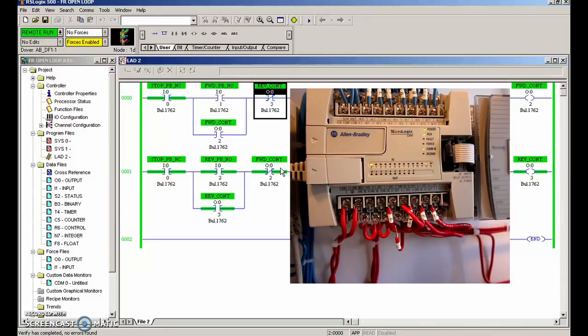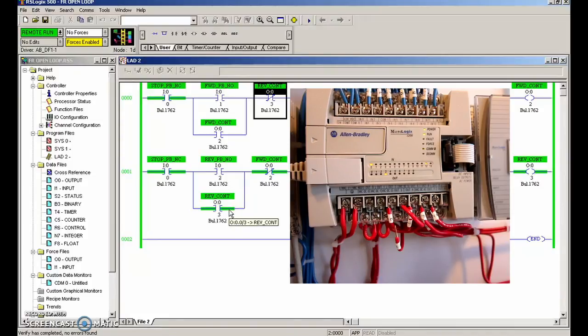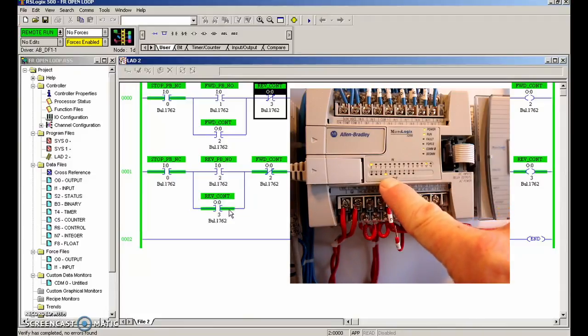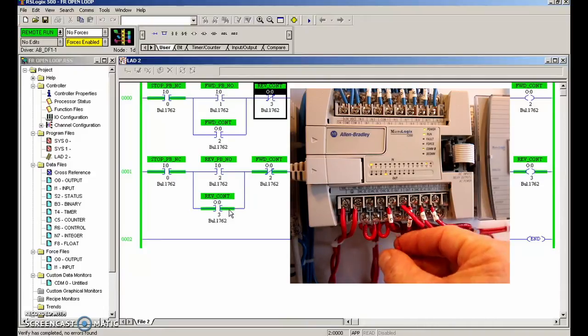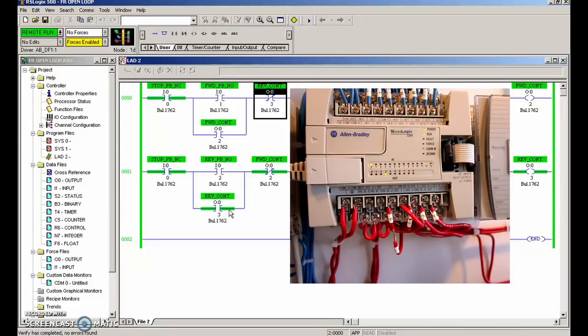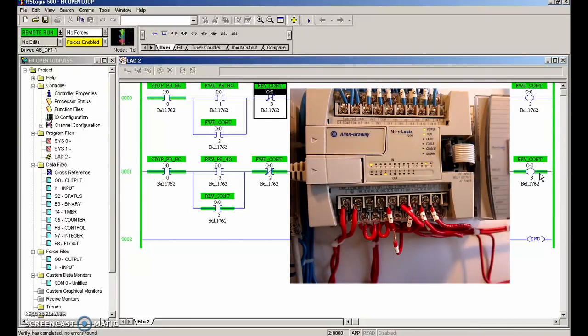Let's try turning on the forward — forward is working. If I turn on the reverse, my program shows it's on but my contactor is not pulling in whatsoever. This shows why we need a closed loop: right now we're using the output address for our holding contact. Output number three is illuminated — there's 24V trying to go out from that terminal — but it can't make it because of the loose connection, and there's nothing to confirm the contactor actually turned on. Let's stop the output from firing before we reconnect, to avoid sparks.